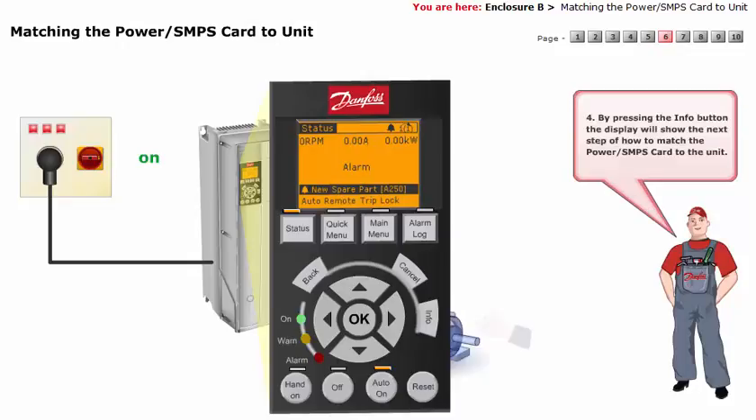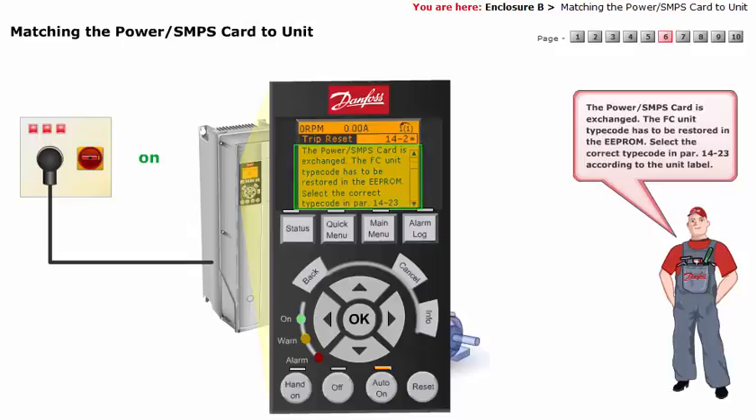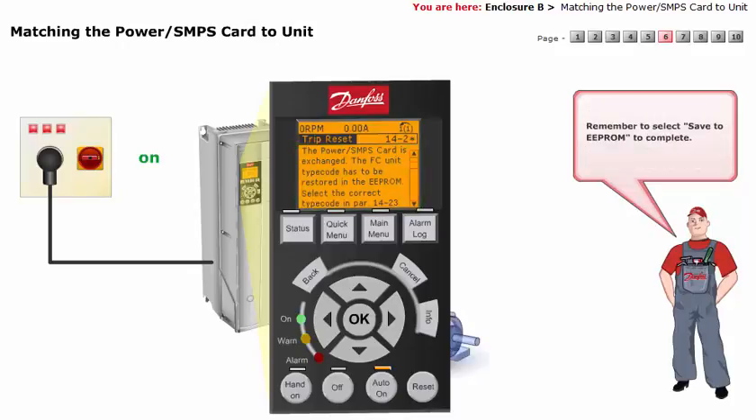By pressing the Info button, the display will show the next step of how to match the power or SMPS card to the unit. The Info text will be as follows: The power or SMPS card is exchanged. The FC unit type code has to be restored in the EEPROM. Select the correct type code in parameter 14-23 according to the unit label. Remember to select Save to EEPROM to complete.